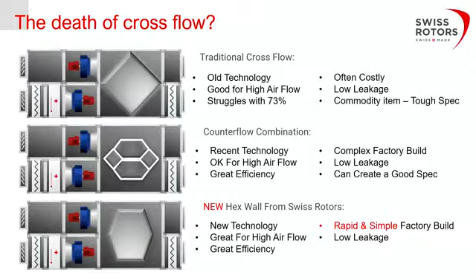So what we'll do now is we'll have a look across some cherry-picked sizes and compare how those stack up against a cross-flow type heat exchanger, the older style technology. So if we look on the screen here, you can see that within a HexWall versus a cross-flow on the very smallest unit that we have, we are better on efficiency all the way across the range, but we are a little bit higher on pressure drop, which you would expect from that longer dwell time inside a counterflow heat exchanger. So how does it compare? So we're a little bit smaller in height than you would get from a crossflow heat exchanger, but a little bit larger in depth. The width, for comparison reasons, is the same, but the efficiency is higher. The cost is 99 euros lower on the smaller model.